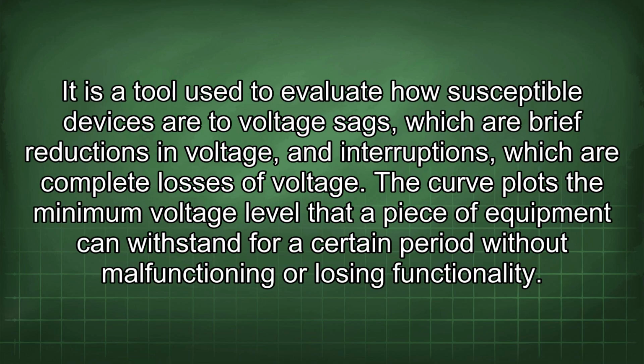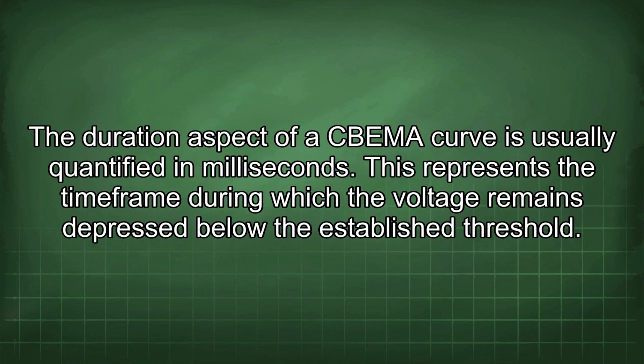It is a tool used to evaluate how susceptible devices are to voltage sags, which are brief reductions in voltage, and interruptions, which are complete losses of voltage. The curve plots the minimum voltage level that a piece of equipment can withstand for a certain period without malfunctioning or losing functionality. The duration aspect of a CBEMA curve is usually quantified in milliseconds. This represents the time frame during which the voltage remains depressed below the established threshold.